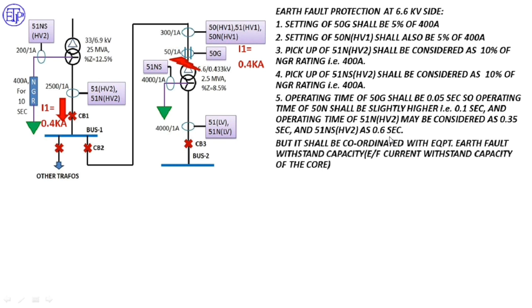It must be remembered — as explained in my previous video — that these relays shall be coordinated with the equipment's earth fault withstand capability, specifically the withstand capability of the transformer core. All pickup and time settings may need to decrease if the earth fault withstand capability of the core is not coordinating with these settings. I will explain this at the end of the video.